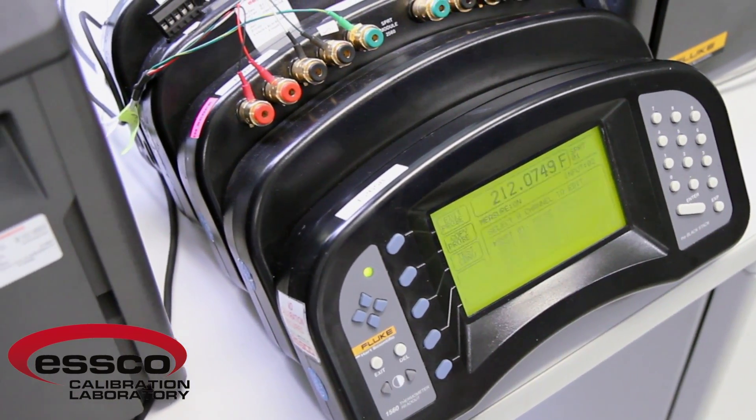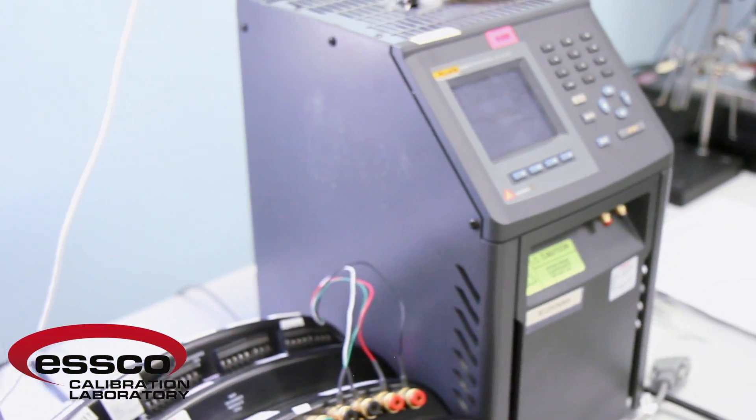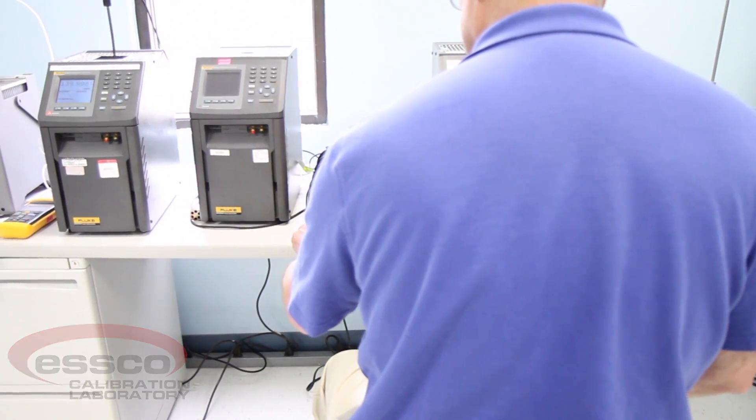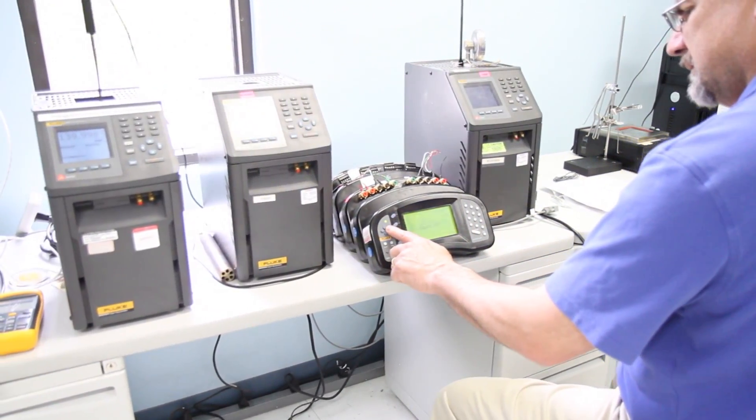The software will automatically go to the next set point once the well is stabilized and records the measurement. It also allows us to provide the customer with the Callendar-Van Dusen and ITS-90 coefficients for RTDs.